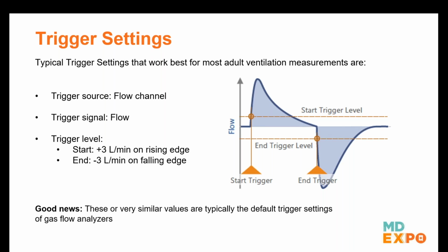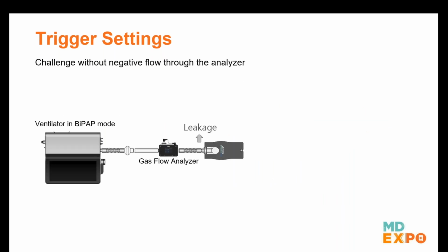However, sometimes it happens that this is not sufficient for your application. Let's have a look at such an example. Here we have a setup for a so-called BiPAP ventilation. Is anyone familiar with BiPAP? BiPAP means the ventilator is applying 2 different pressure levels to the test lung. In this setup, we have a defined leakage in front of our test lung. This is to simulate a typical non-invasive patient interface with a mask, for example, that has a defined leak.